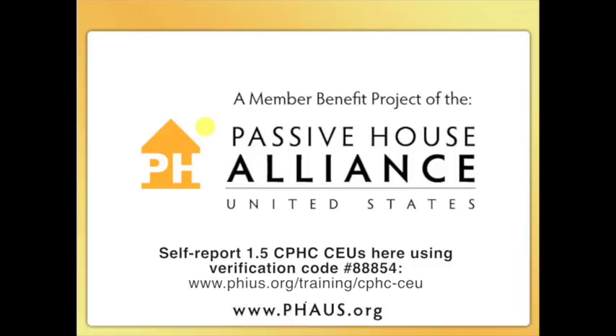Okay. Enrique asks, has anybody developed a formula to calculate the cooling time without heat in an outage event? Yeah, I mean, you can estimate a building time constant. If you've got a number for the thermal mass of the building and the average U value, it's basically the product of those, or the ratio of those.